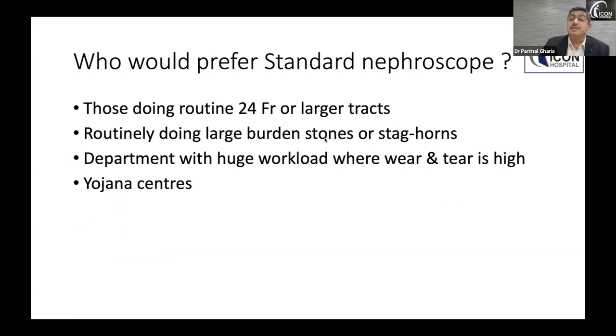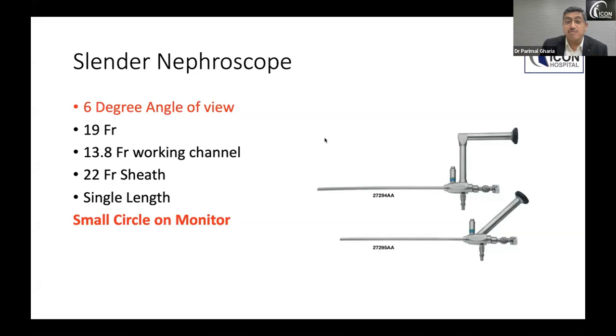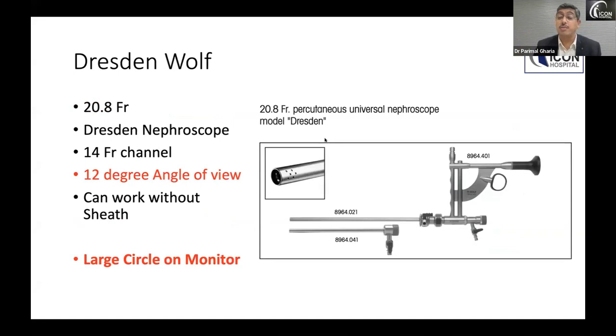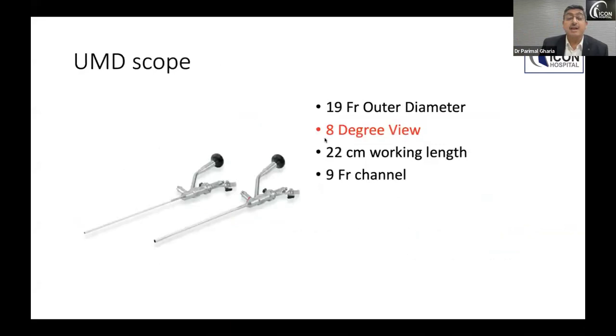Then comes a slender nephroscope. Routine is a Storz nephroscope of 19 French. It has a 6 degree angle of view. The only problem with this scope is that it has a very small circle of view on the screen, so it has to be taken care of previously. Then there is the Dresden. The most favored nephroscope of all urologists is the Dresden nephroscope. It's 20 French. It can easily go into a 22 French plus tract. It has a very good large circle on the monitor and a comfortable viewing angle also, 12 degree. Then there is the MIP-L, and another scope is the UMD. It has a 19 French diameter.